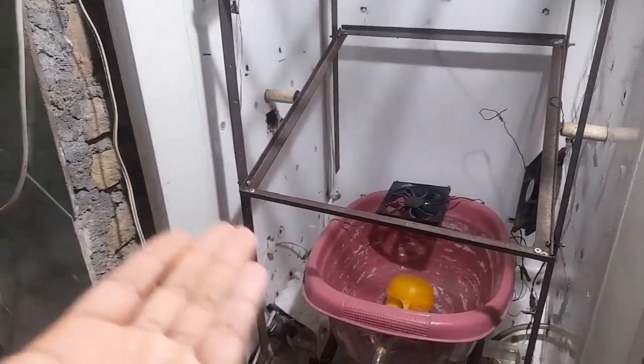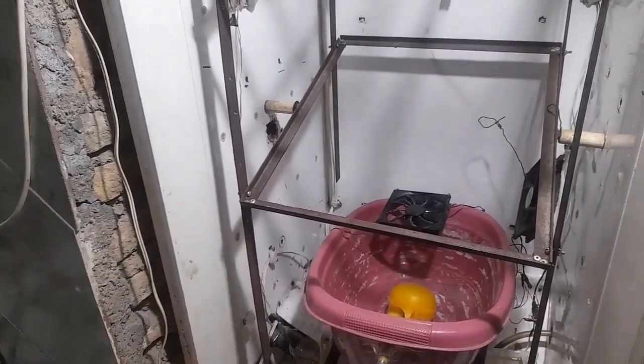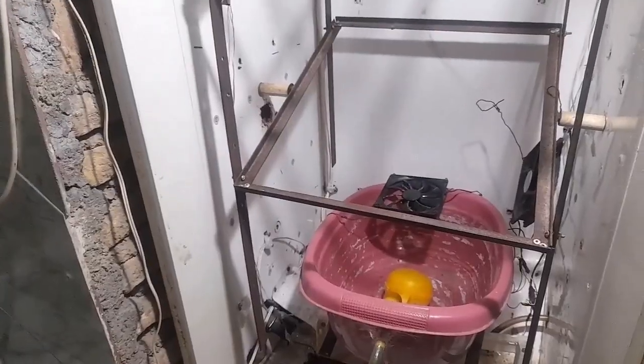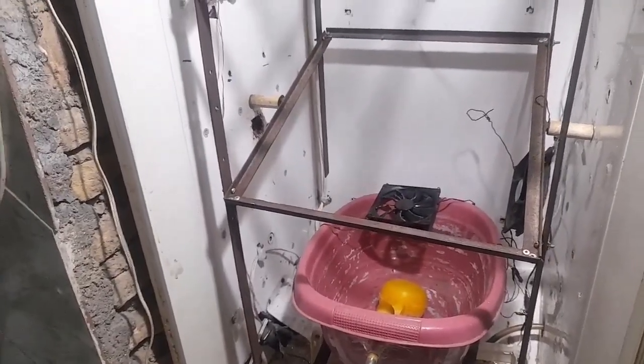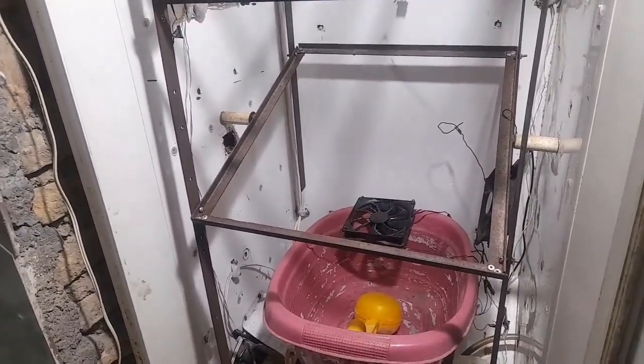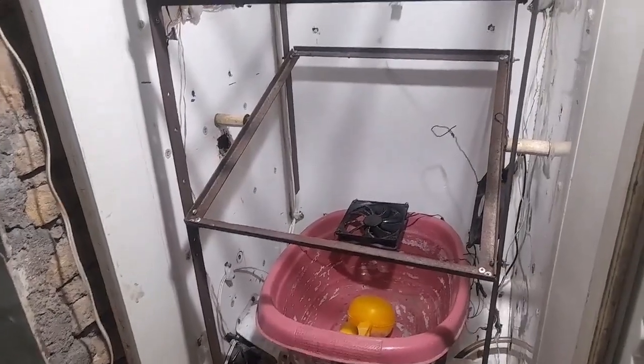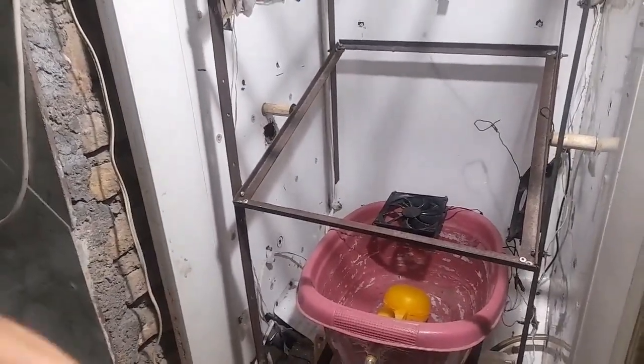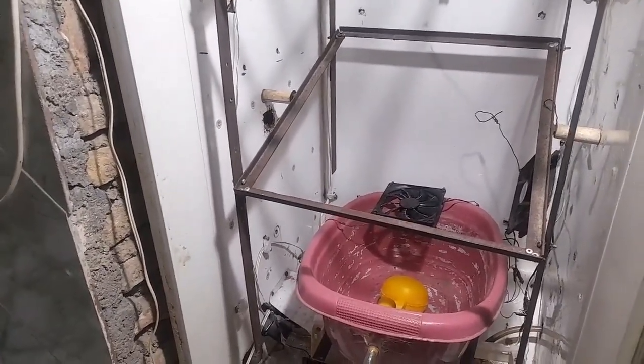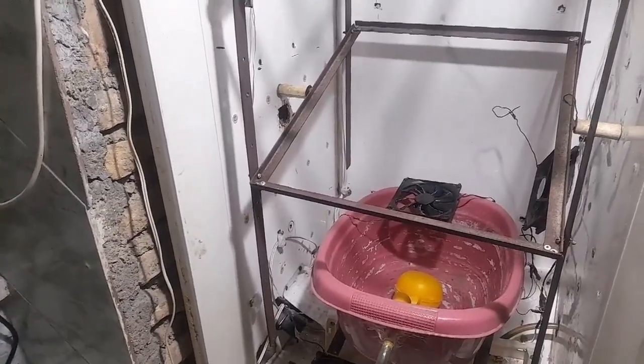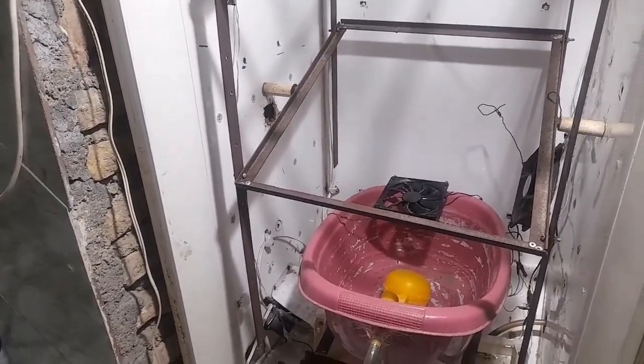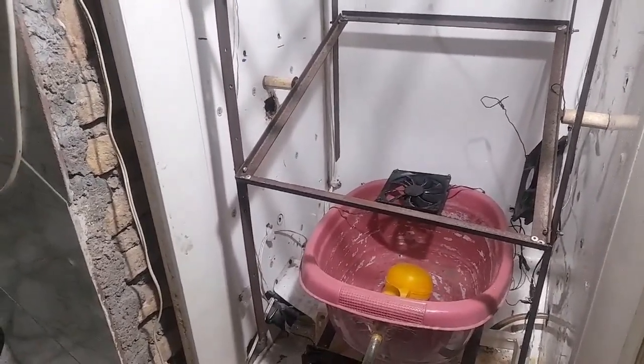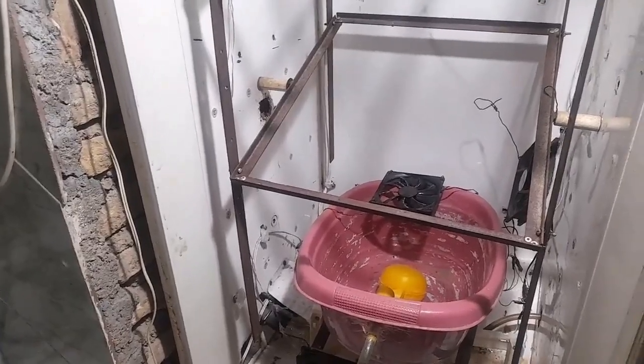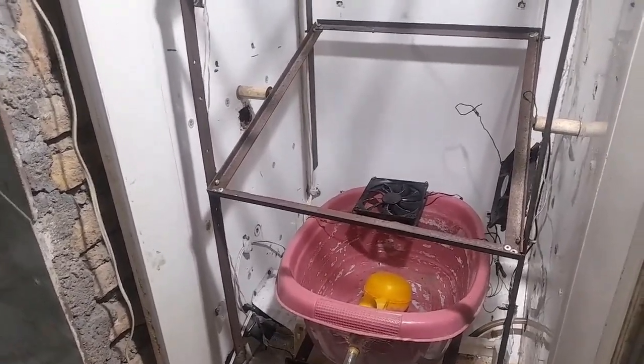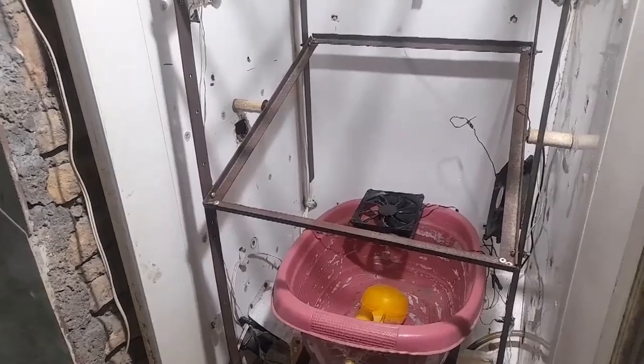You might think distilled water solves the problem. While it certainly helps, using distilled water continuously becomes expensive and simply isn't practical for most incubators. Even boiled water still contains dissolved minerals, so it doesn't completely eliminate the issue. With normal tap water, an ultrasonic humidifier may fail after a relatively short period of use. Even if you improve the water quality, its lifespan is still limited. For me, the maintenance cost and replacement frequency simply aren't worth it.